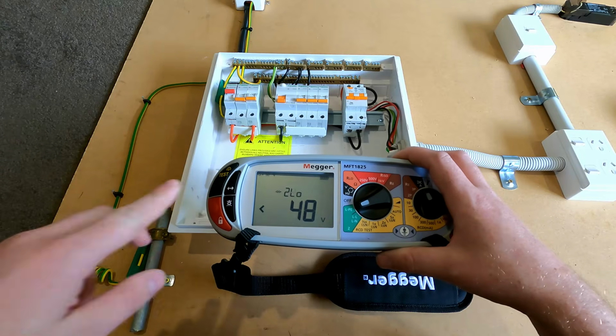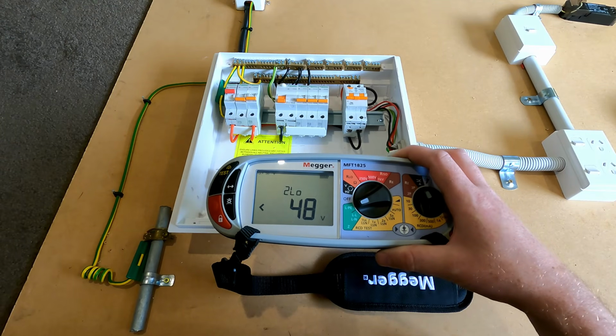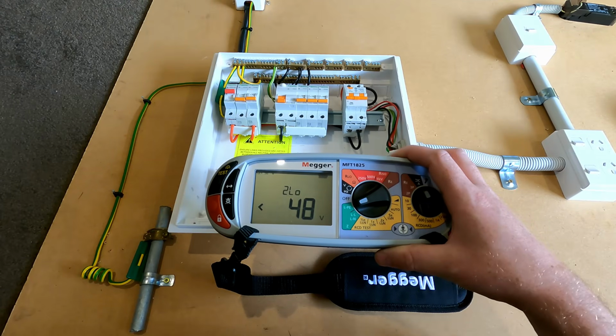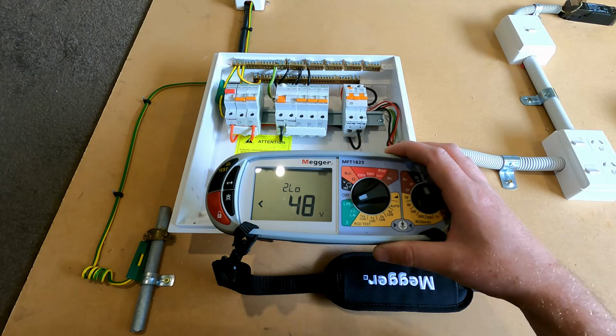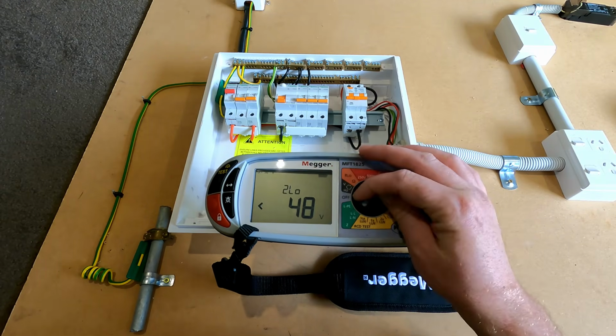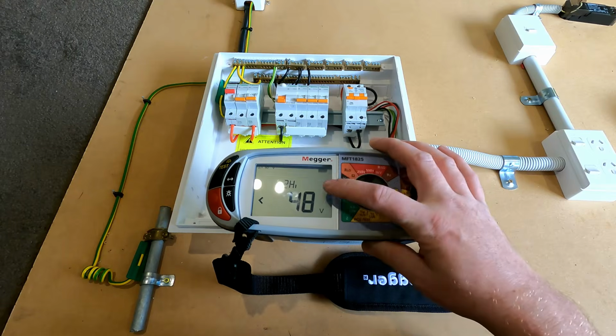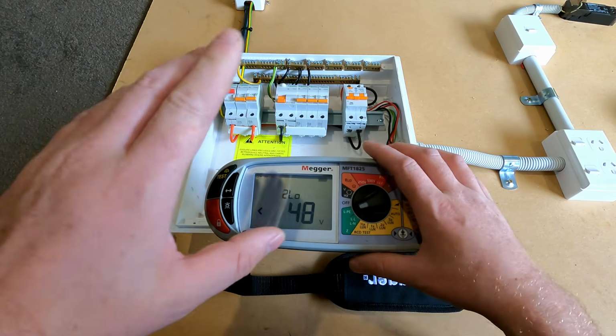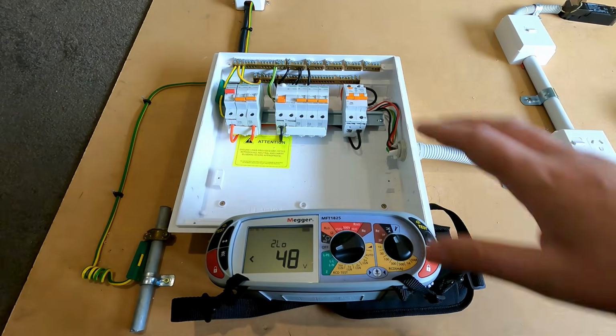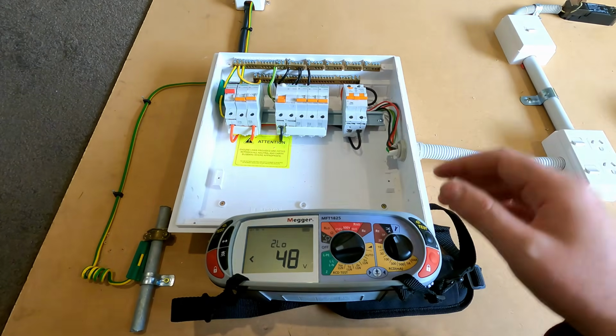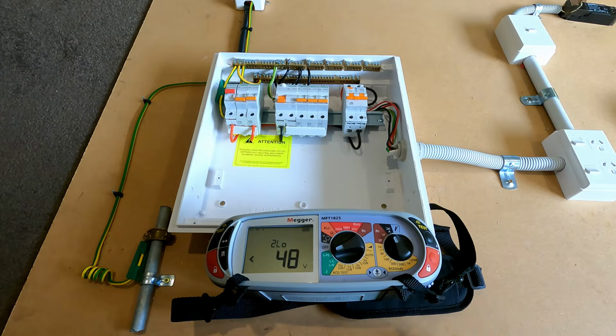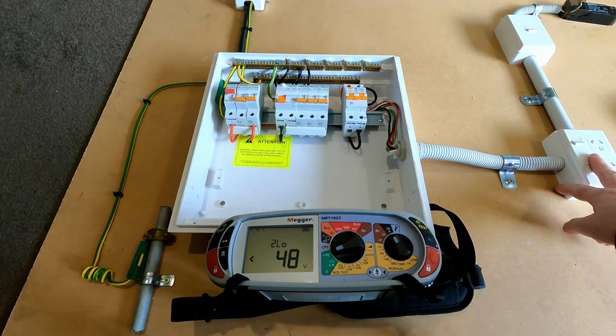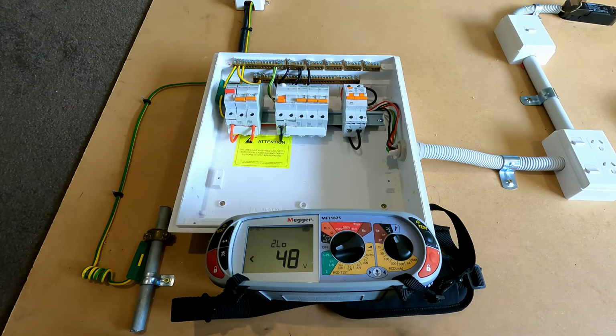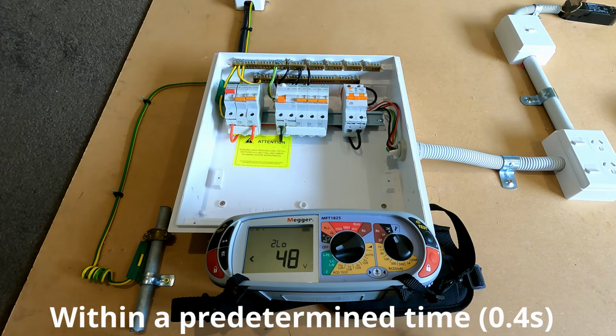Now the next one is your 2 low, and you shouldn't really be using this test. What it's designed for is if you've only got phase earth available and you need to do a low current test somewhere. Now on here, flick it to line neutral. The only test available is your 2 lead high current test. So when we're doing these tests, we want to do one at the switchboard to ensure that the circuit protection is going to work under fault conditions, and then we do our second test at the furthest socket from the installation to ensure that the longest path has an impedance low enough to operate the circuit protection under fault conditions.